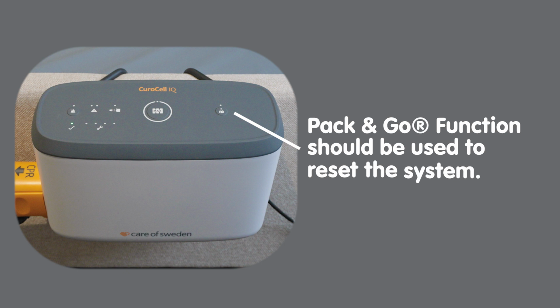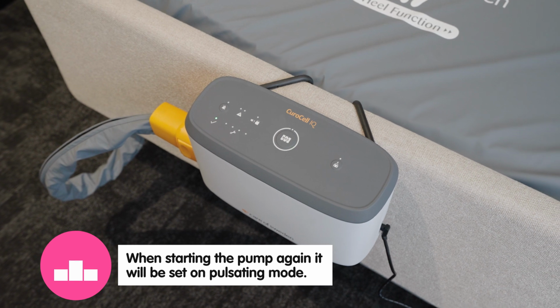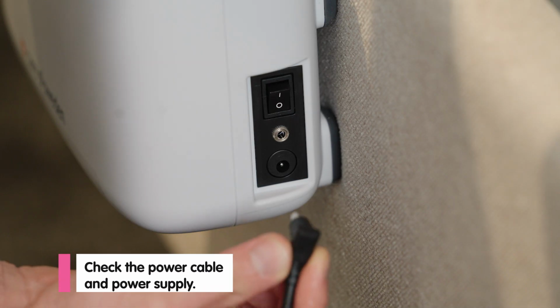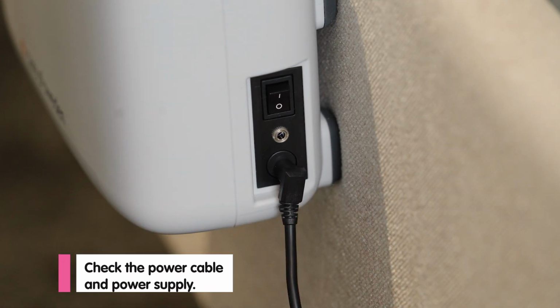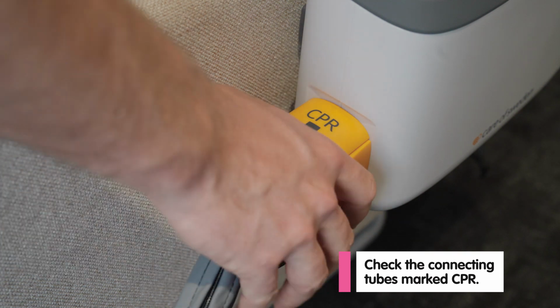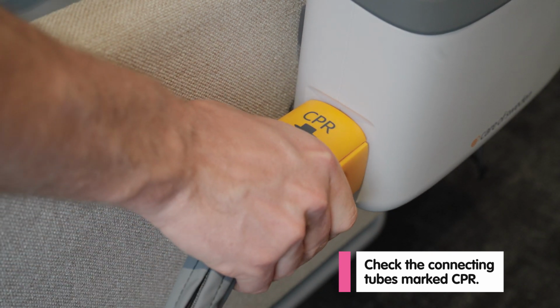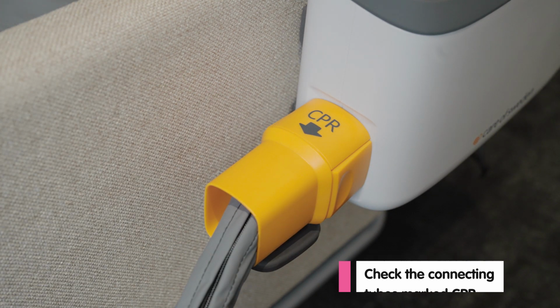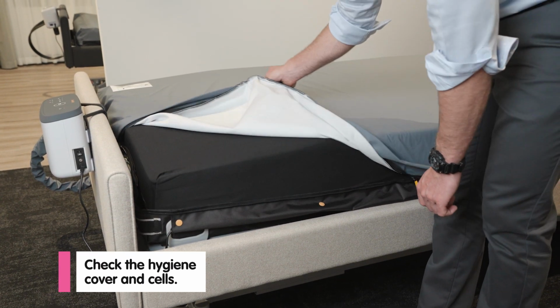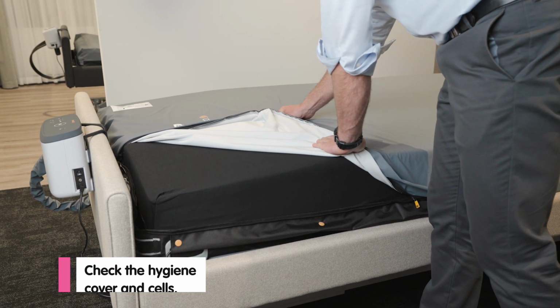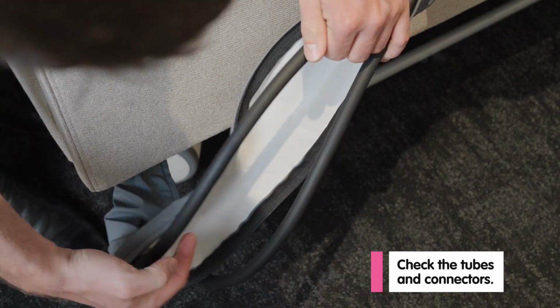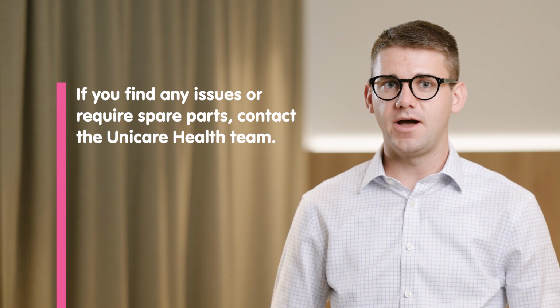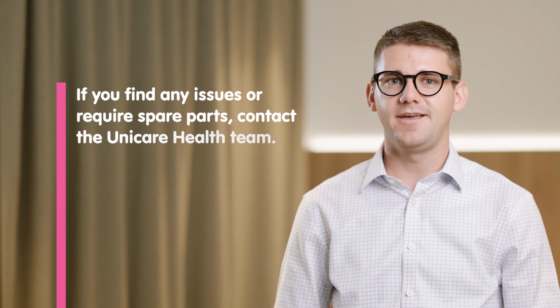Between users, the pack and go function should be used to reset the system. When starting the pump again, it will be set on pulsating mode. You should also check that the power cable and power supply are undamaged, the connecting tubes marked CPR on the side of the control unit are positioned correctly and not leaking, the hygiene cover is intact and the cover and cells are correctly assembled, and no tubes or connectors are damaged or jammed. If you do find any issues or require any spare parts, contact the friendly team at Unicare Health.